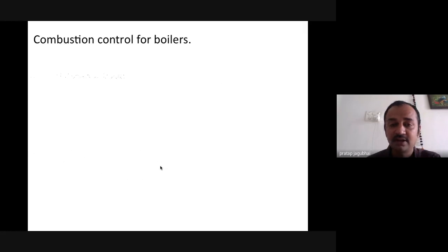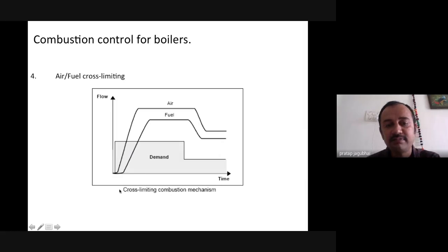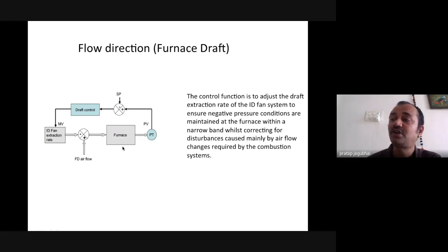So for that, we should keep in mind that based on the demand signal, pressure and flow, the air should always lead the fuel. Though it's a tighter control, and we should keep the tighter control from the auto trim point of view, we should ensure that air is sufficiently available to control the combustion and keep a safe combustion in place. That's why it is called cross limiting.